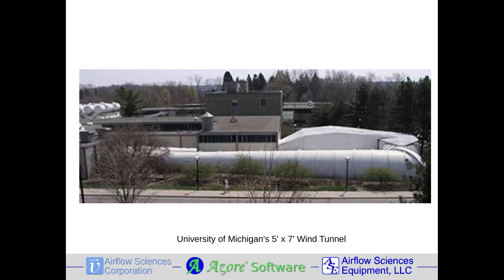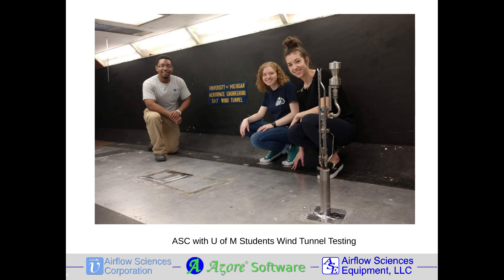To facilitate calibration of the PM10 probe, Airflow Sciences teamed up with the Aerospace Engineering Department at the University of Michigan for the use of their subsonic, low-turbulence, 5x7-foot wind tunnel. This large tunnel is capable of velocities up to 250 feet per second with its 1,200 horsepower motor. While not large enough to hold a full-scale vehicle, its size is more than sufficient to ensure a minimal amount of probe blockage, in this case 0.3%.